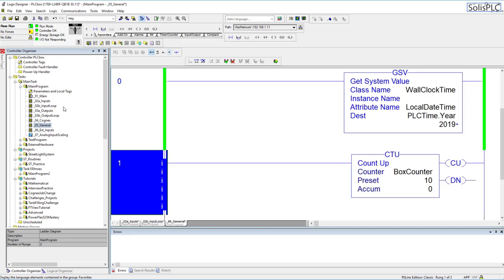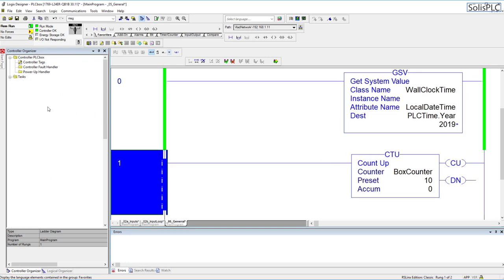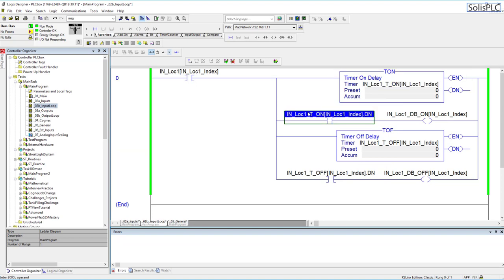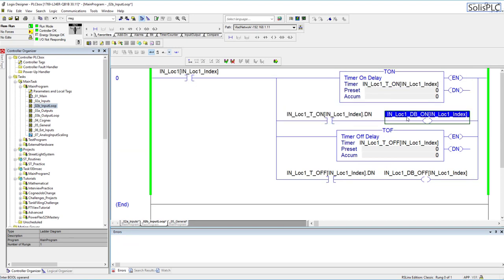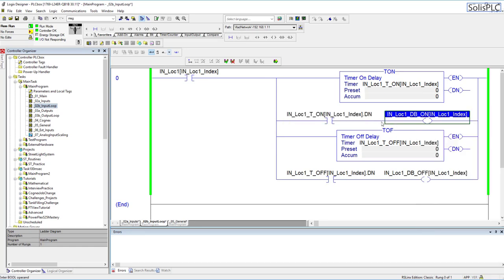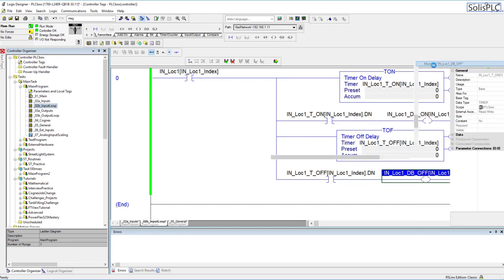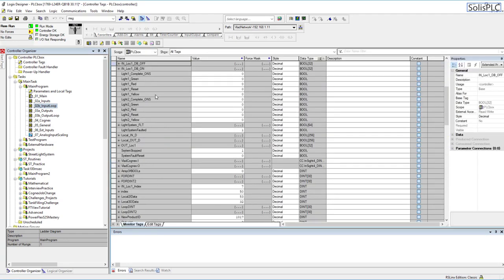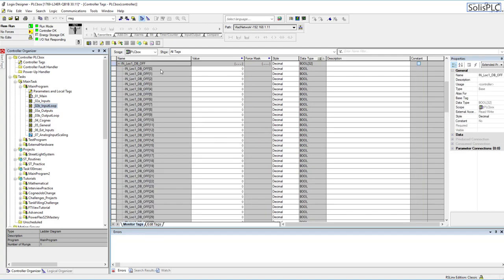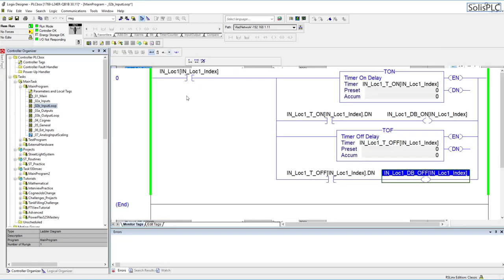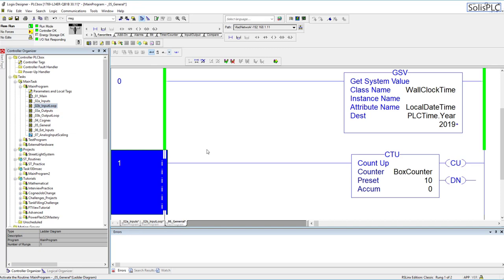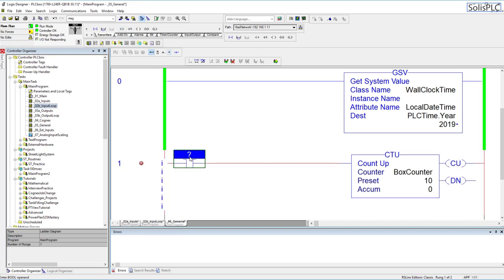I'm going to go back into my input loop and double check that once my timer is done I should be calling this tag. My timer needs to be off for 500 milliseconds so it's going to be this tag. I'm going to monitor and then I'm going to go into this first tag. I'm going to add an xic instruction. Think of this as the same input that we have our sensor on except that it needs to be off for 500 milliseconds before it counts box.